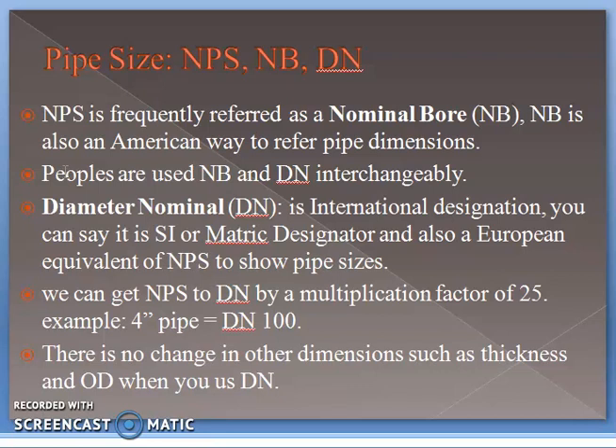We can convert NPS to DN by a multiplication factor of 25. For example, a 4-inch pipe in NPS multiplied by 25 gives DN 100. There is no change in other dimensions such as wall thickness and outside diameter when converting from NPS to DN.